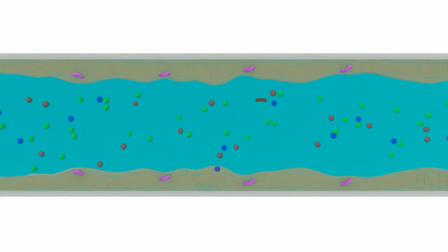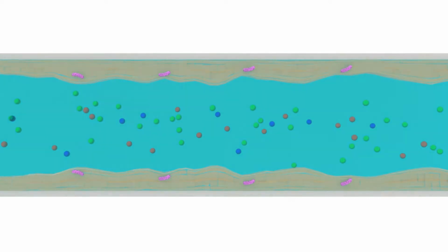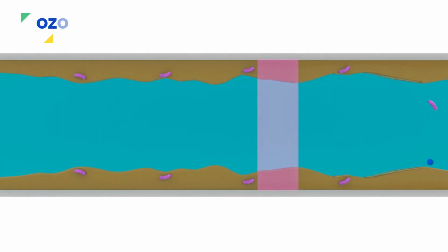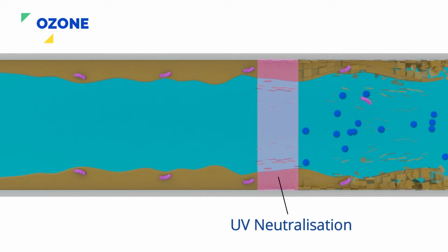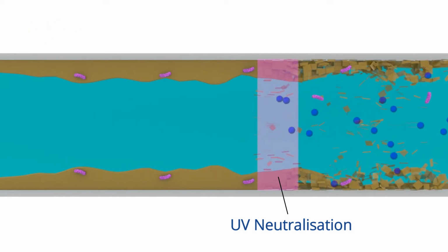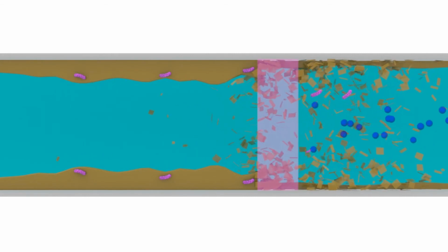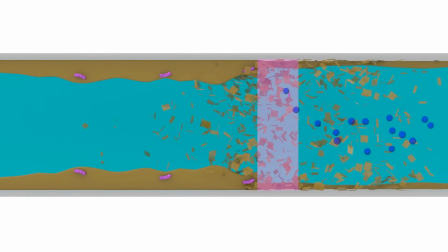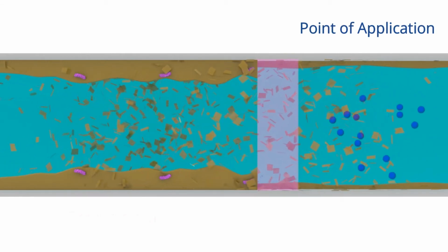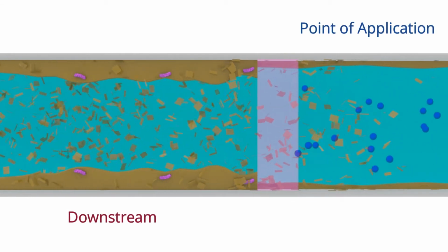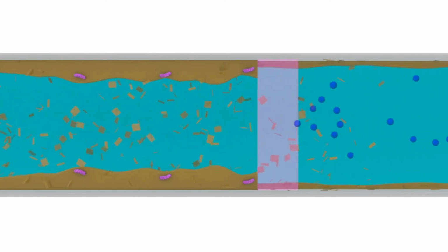When compared to other oxidizing biocides, the advantages of chlorine dioxide are widely proven and documented. For example, ozone is a highly reactive biocide, but in many applications is purposefully neutralized via UV lamp due to its toxicity. Even in applications where neutralization is not required, the chemical still has a short half-life, making it only really effective at the point of application. This means there is the risk of insufficient downstream biocidal protection beyond the unit. By contrast, longevity is really where chlorine dioxide shines.